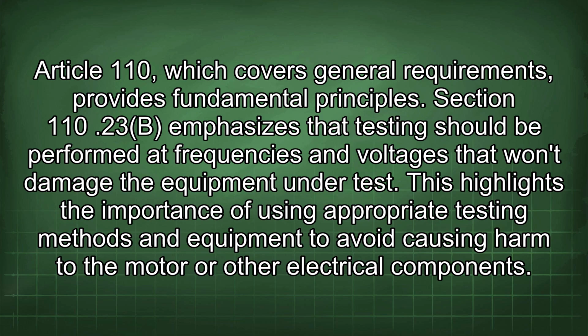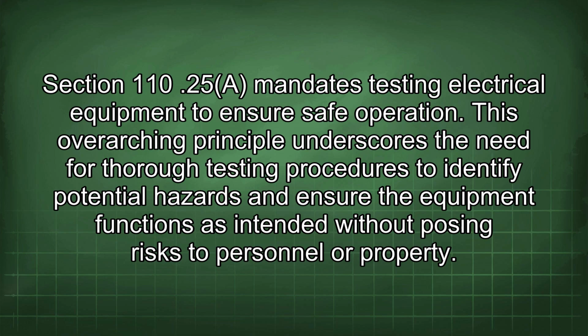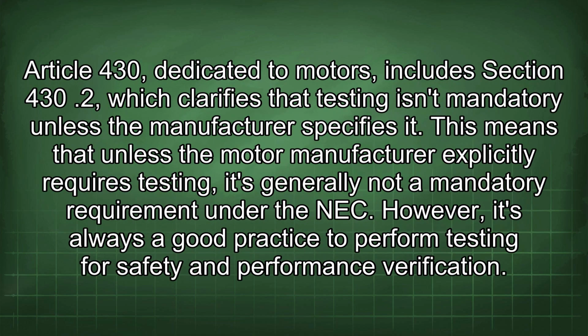electrical components. Section 110.25(A) mandates testing electrical equipment to ensure safe operation. This overarching principle underscores the need for thorough testing procedures to identify potential hazards and ensure the equipment functions as intended without posing risks to personnel or property. Article 430, dedicated to motors, includes Section 430.2, which clarifies that testing isn't mandatory unless the manufacturer specifies it. This means that unless the motor manufacturer explicitly requires testing, it's generally not a mandatory requirement under the NEC. However, it's always a good practice to perform testing for safety and performance verification.